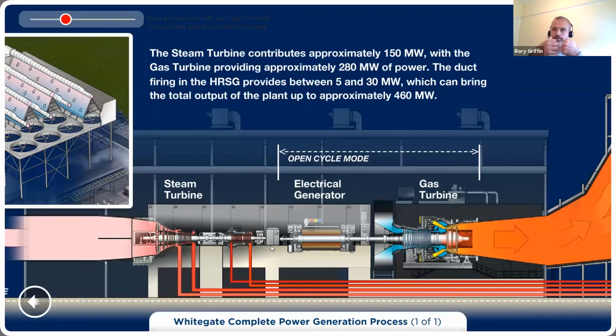What that allows is a small bit of give in the axial direction, so that if you have to lift out turbines, the whole thing isn't rigidly bolted together. So there's a little bit of give between the generator and the HP turbine. There is, so that's bearing 5, we've bearing 6 here, we've a load coupling, and bearing 7, and finally bearing 8 is inside in the condenser of the machine.